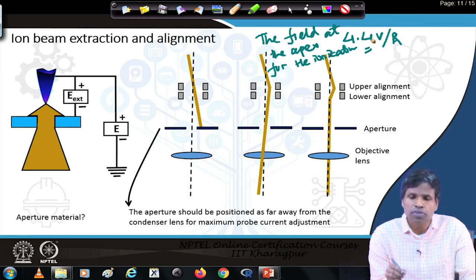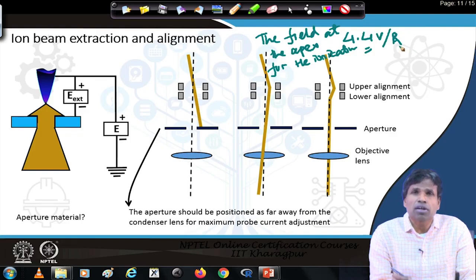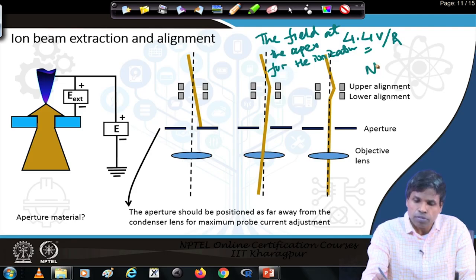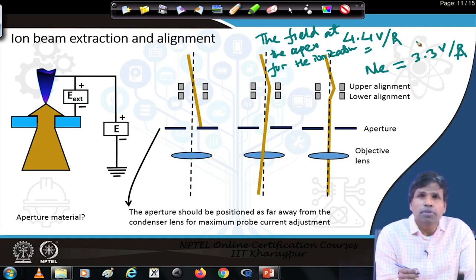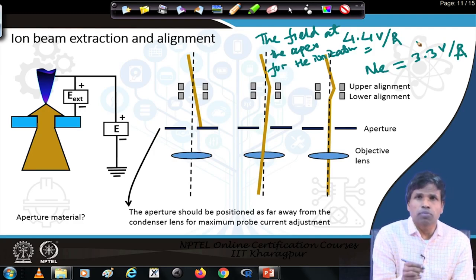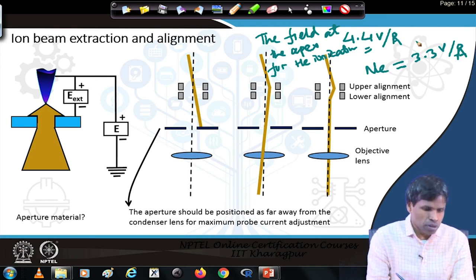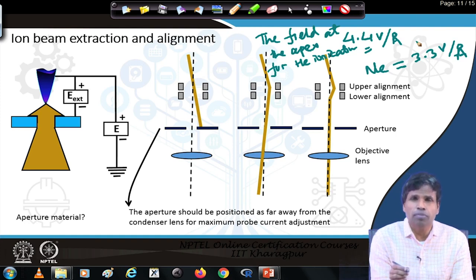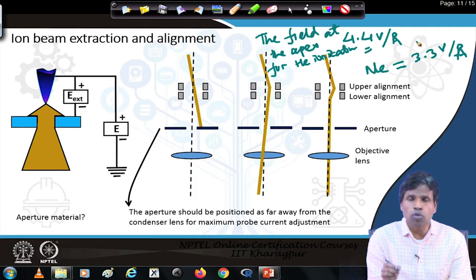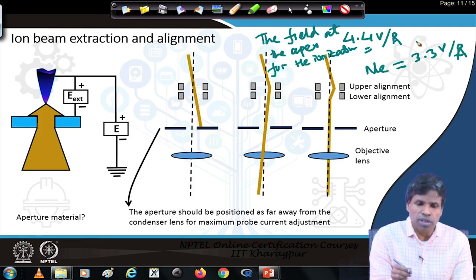Once a trimer is formed, the field at the trimer surface should be at 4.4 volts per angstrom to efficiently ionize the helium atoms. For neon, the field is supposed to be 3.3 volts per angstrom. When this potential is maintained at the tip, ions can be efficiently extracted from the apex and brought downwards. The extraction voltage is also used to ensure there are no stray individual atoms sitting around the tip — a slightly higher voltage will evaporate those, forming a very well-defined trimer. Microscopy work begins only once the trimer is confirmed inside the microscope.